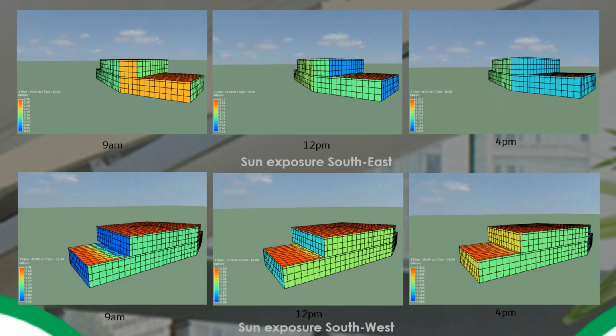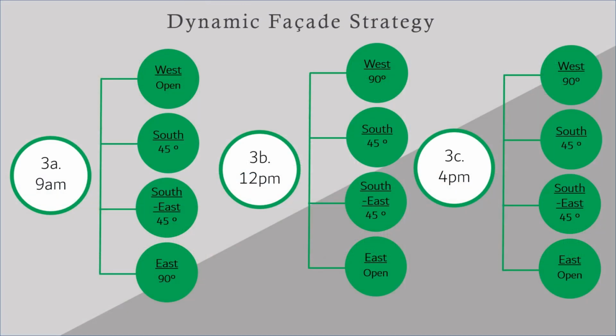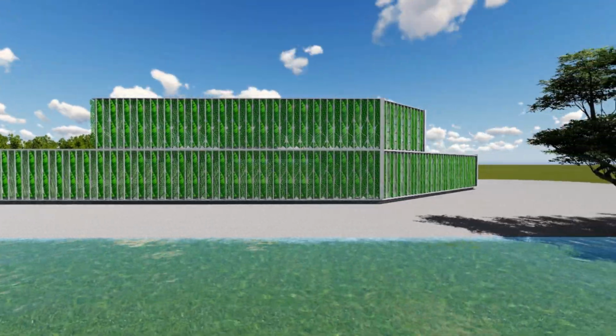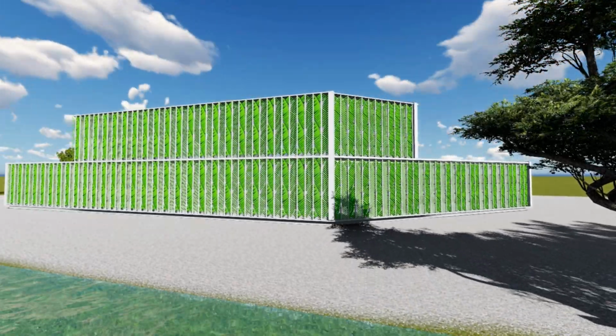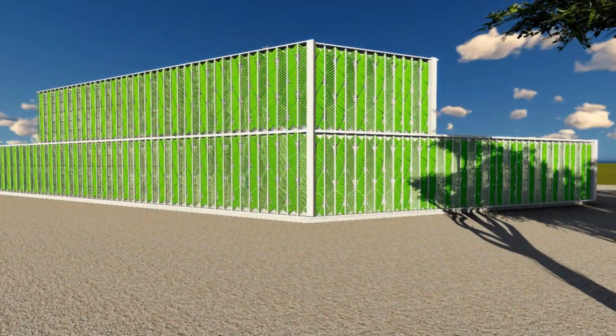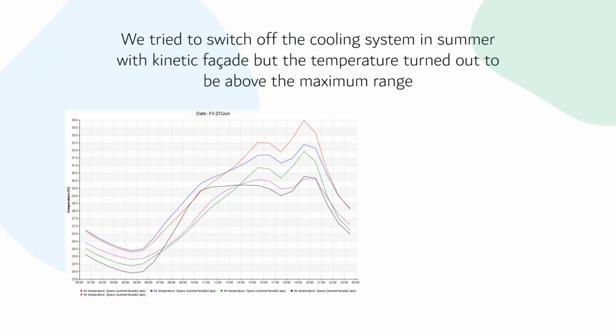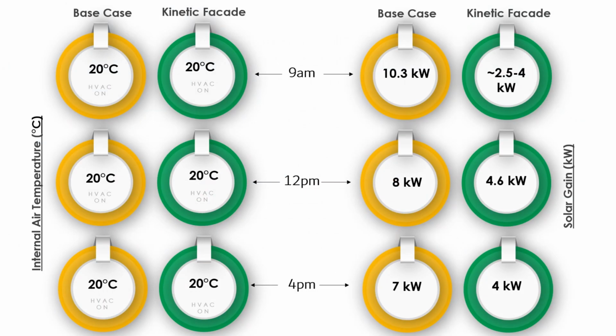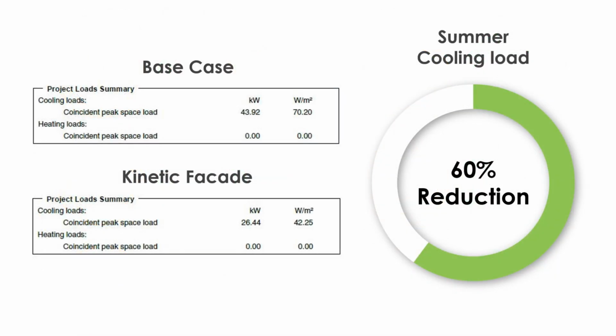In summer season, we derive the facade strategy based on the sun exposure analysis. We tried to switch off the cooling system in summer with kinetic facade, but the temperature turned out to be above the maximum range. So we turned on the cooling system for both cases due to greenhouse effect, keeping internal temperature consistent but reducing solar gain to a significant amount to regulate overheating. Through this strategy, we have reduced 60% cooling load in summer.